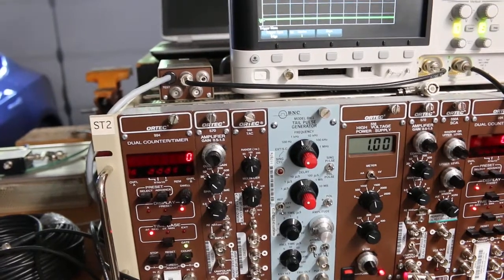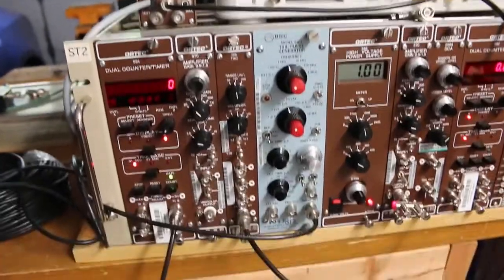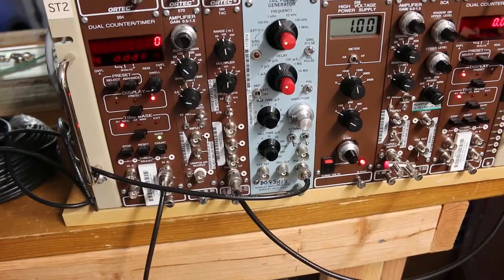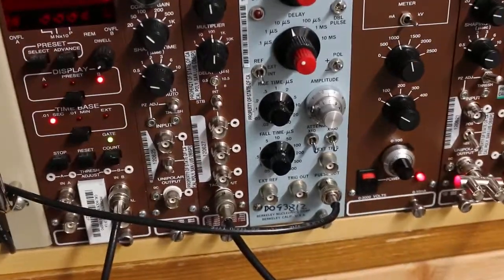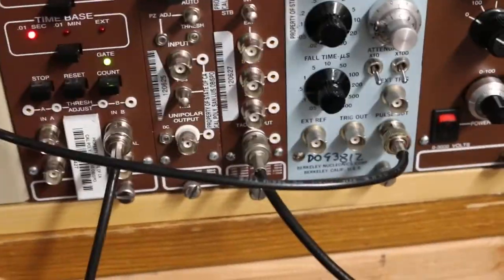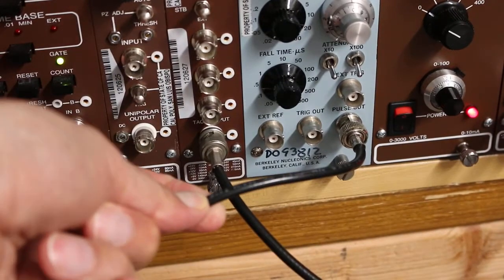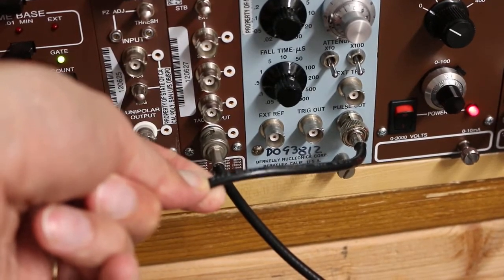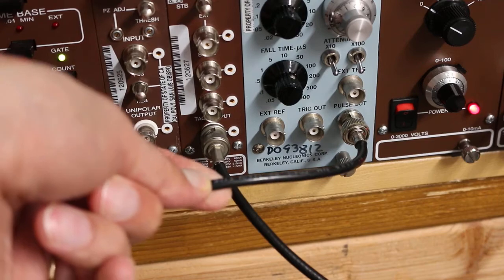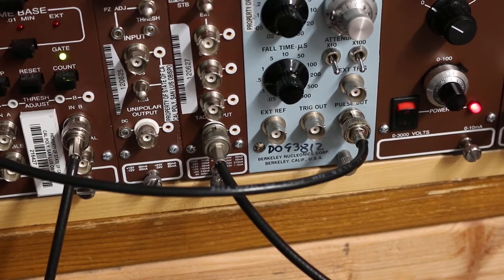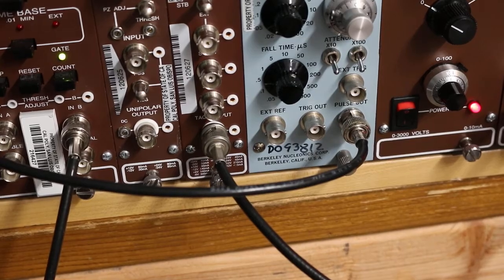Okay, so what are we going to drive it with? Well, now you see the value of that LED cable that I mentioned is going in to the detector as well. So this cable right here is connected to that LED, which is positioned right next to the scintillation plastic inside the detector. So when the LED flashes, it sends some light through the scintillation plastic and is picked up by the photomultiplier tube, sort of like a fake nuclear event.